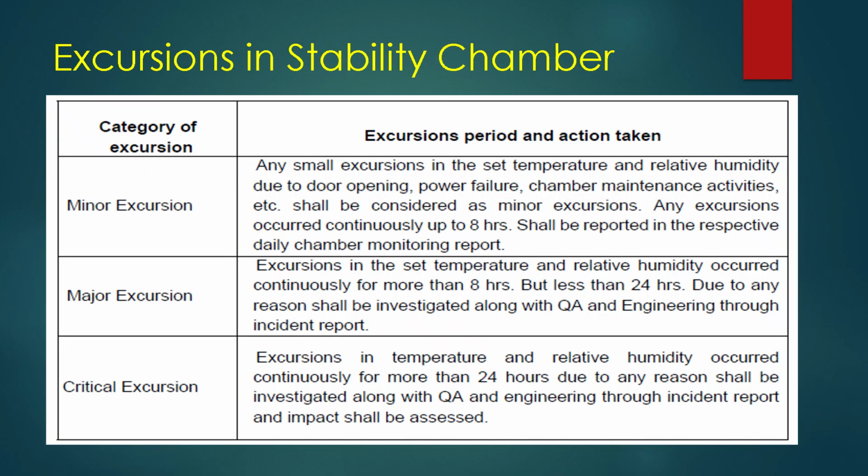In case an excursion occurs in the set temperature and/or relative humidity of the stability chamber due to any reason like breakdown, power failure, door kept open for a longer time, etc., it can be categorized as per the provided table and action to be taken as specified.